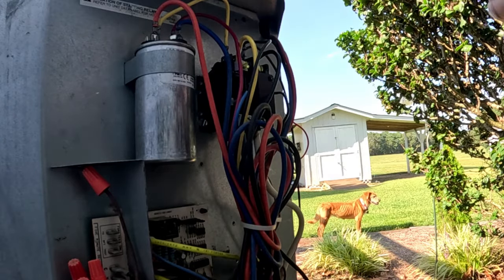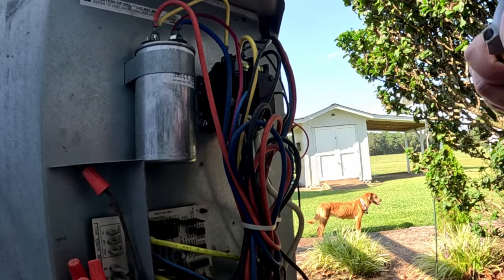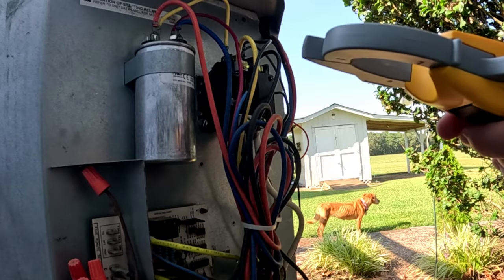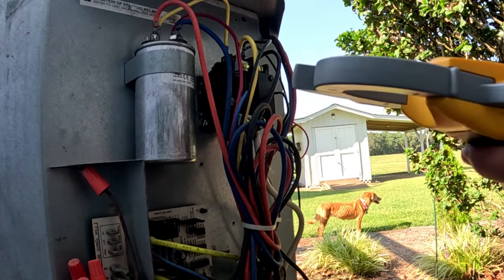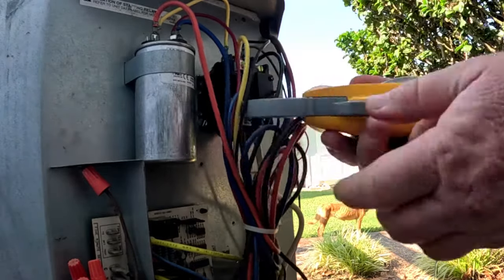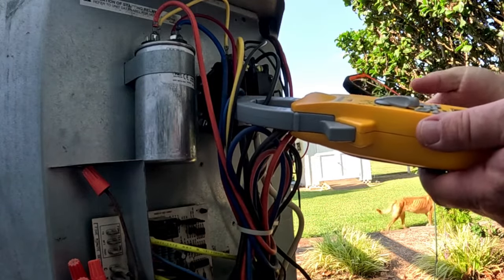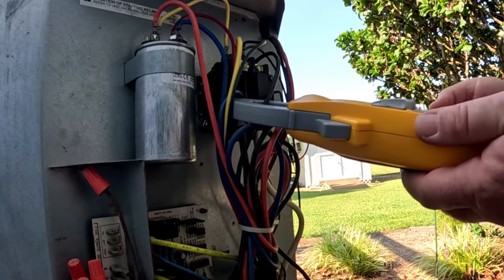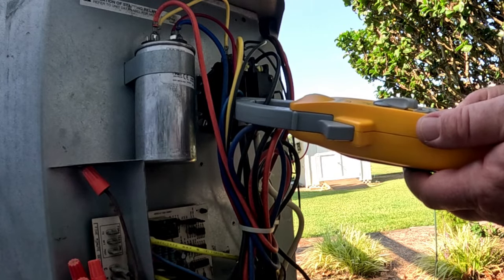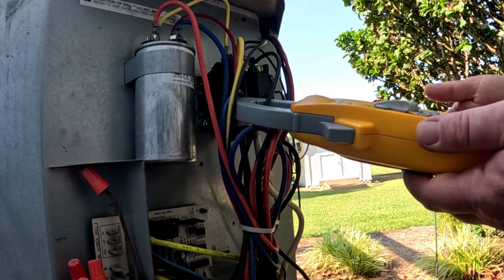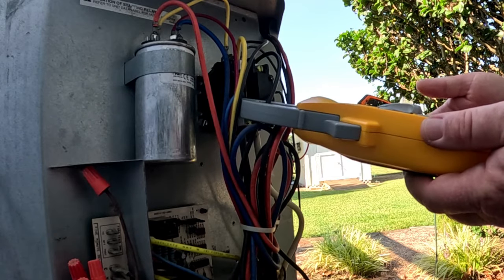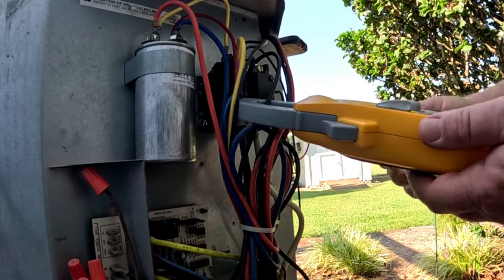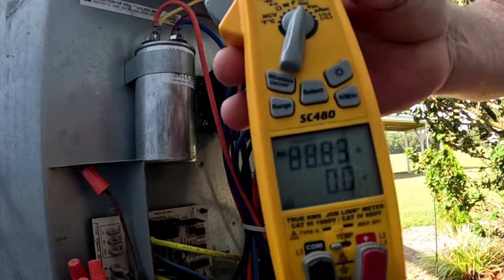So it showed an inrush of 85. So let's go see what the FieldPiece does. Alright guys, this unit's been off for about 10 minutes, since it wasn't running when I originally turned it on to check that inrush. Refrigerant pressures have stabilized, obviously. So now we're going to check the inrush again, but we are going to use the FieldPiece. And let's turn it back on and see what type of inrush we get this time. Set the temperature down. Huh. So it is fairly accurate. Close. 88.